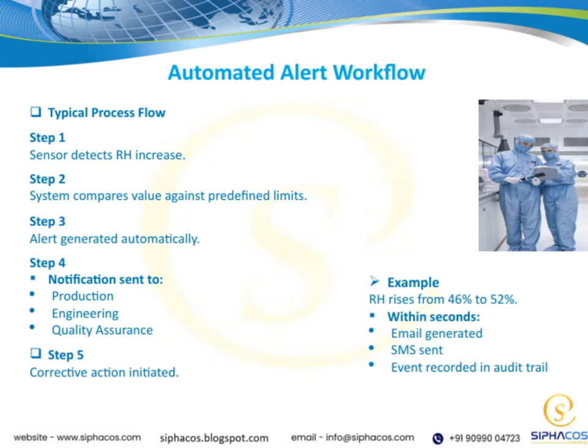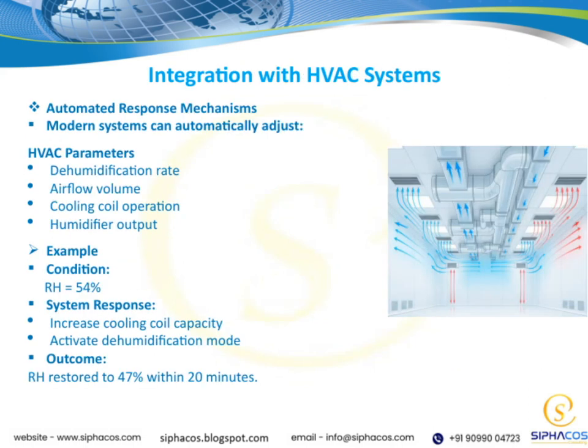Let's look at how modern HVAC systems integrate automated responses to keep indoor air just right. These systems can adjust key settings like airflow, cooling coil operation, and humidifier output without any manual input. For example, if the relative humidity rises to 54%, the system ramps up the cooling coil and switches on dehumidification. The result? Humidity drops back to a comfortable 47% in just 20 minutes. It's a smart, seamless way to maintain ideal conditions.